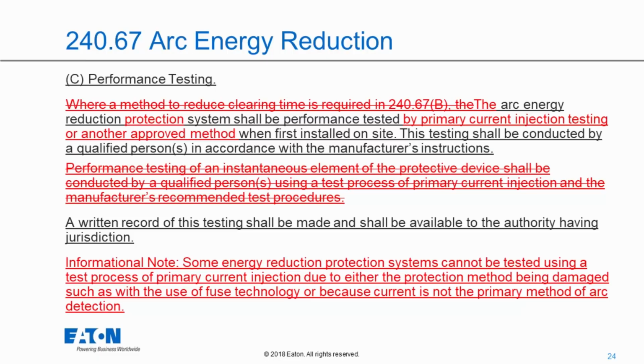So if you don't have a document, it never happened, right? You have to have that written record. And then they offered an informational note on why we have the allowance for another approved method. And that's because some energy reduction protection systems cannot be tested using a test process of primary current injection due either to the protection method being damaged, such as the use of fuse technology. Perhaps you had a fuse limiter. Obviously, you don't want to run current through that, prove the fuse does what you expect it to do, and then have to replace that fuse.